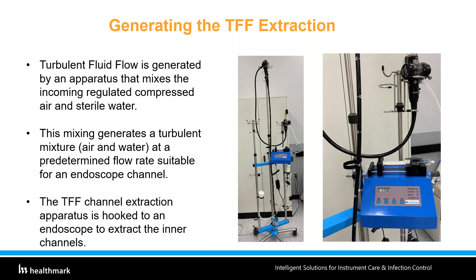So when we looked at this, we said, wow, we obviously need a technology that is self-sufficient, and moreover, that you don't need extra hands, especially nowadays, when you don't have extra hands in the hospital. What can we do? What we did is call it TFF, turbulent fluid flow. Basically you mix the air and water together and create a shear effect that you can use to create a sample. The turbulence generates pressure and a shear effect of that air and water that causes it to go inside the various channels and remove the debris. As I indicated, that is a self-contained device.